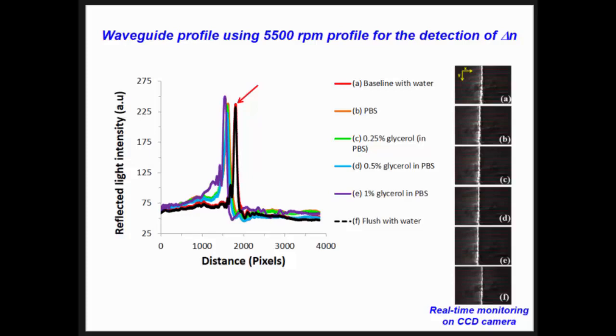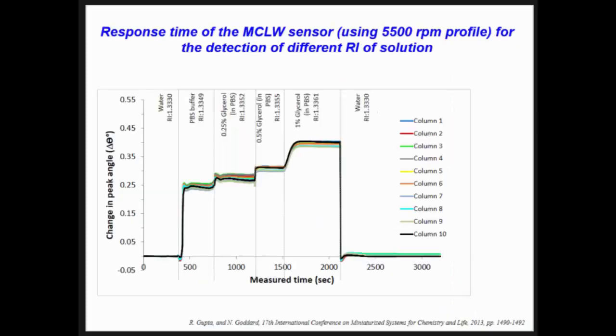If you can see here, I just want to highlight from the baseline with water, you see this is the peak. But at the end of detection, after we changed a few buffers here, at the end we flushed away with water, and we can see it remains at the same position. So this is what we monitor on the CCD camera. So meaning that the binding is so good, and the hydrogel fits very well on the substrates, and it does the job. And in terms of real-time monitoring, this is the response time when we convert to the change in the angle. So each of the buffer changes is good, and shows the diffusion time is very short.